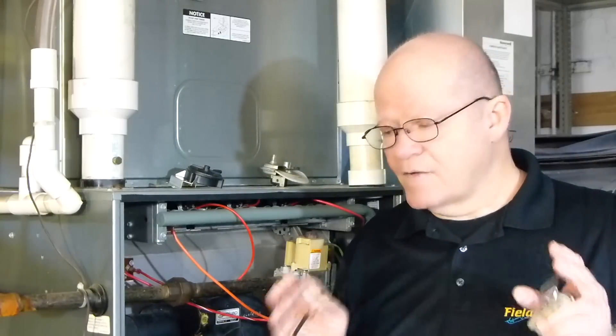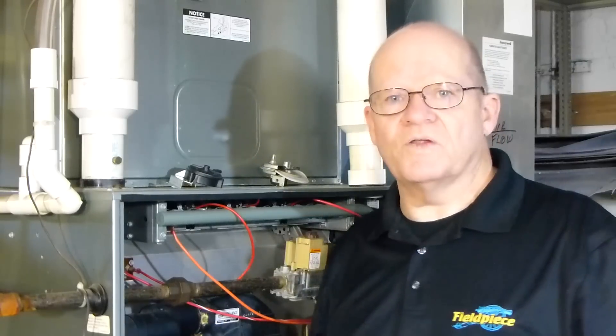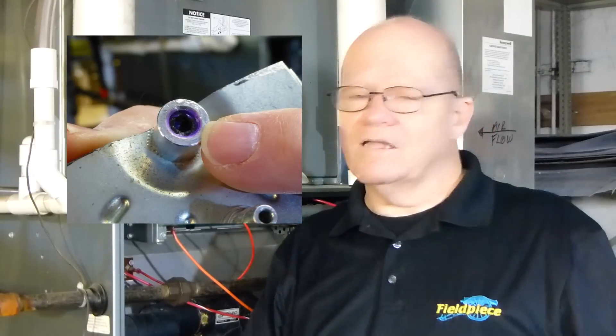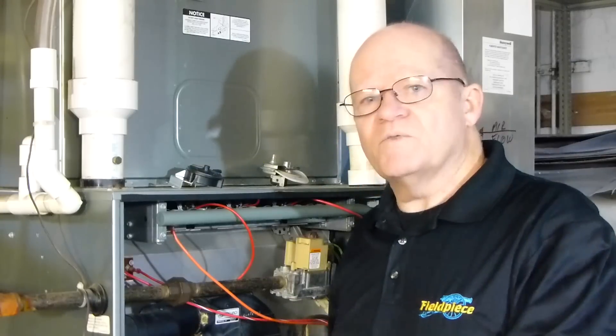Hi, I'm Rich with Fieldpiece Instruments and today I'd like to share a little information about pressure switches. A lot of you have been asking me: can you recalibrate a fixed pressure switch, one that comes with the furnace? Remember that it is actually a fixed pressure switch. Those pressure switches usually have a wax coating on the inside where you can't really calibrate it unless you take the wax out, or it's got silicon in it that prevents you from doing this.